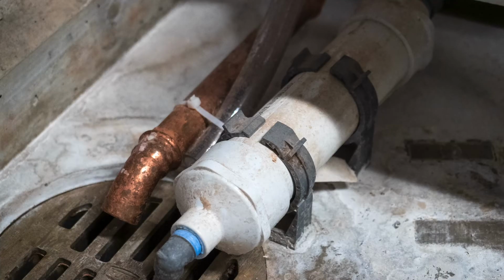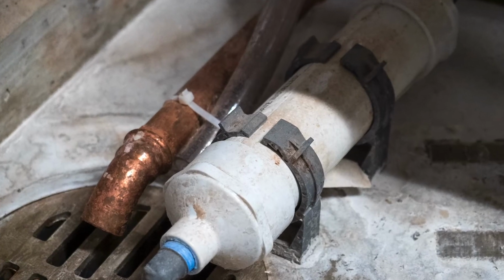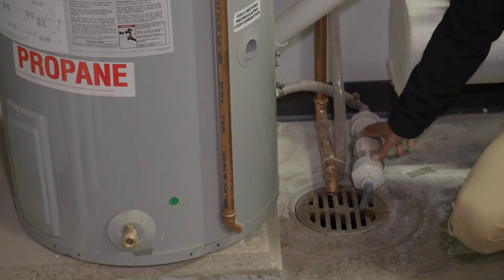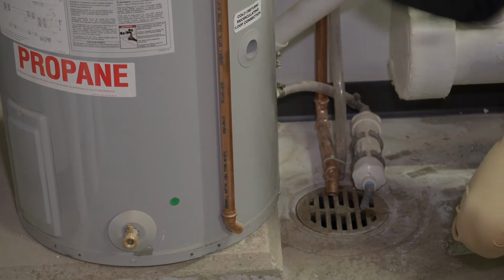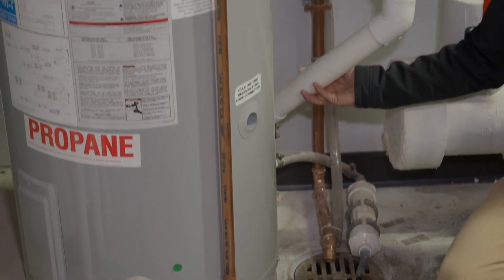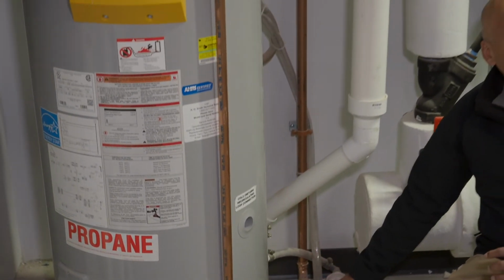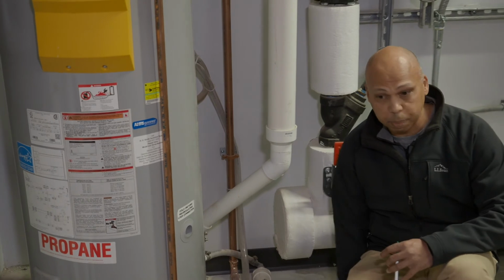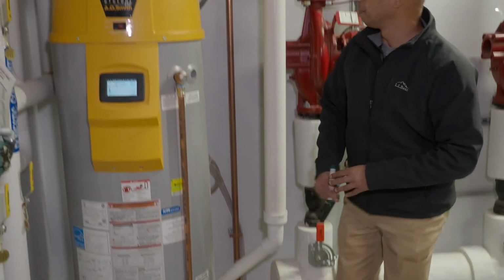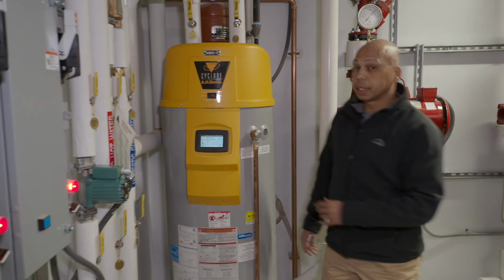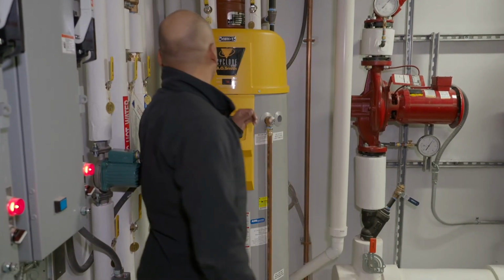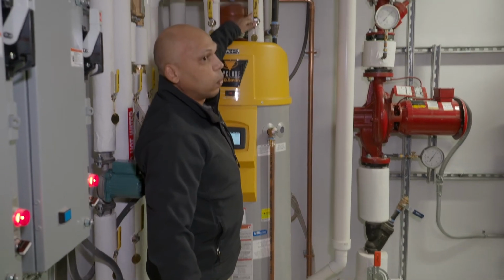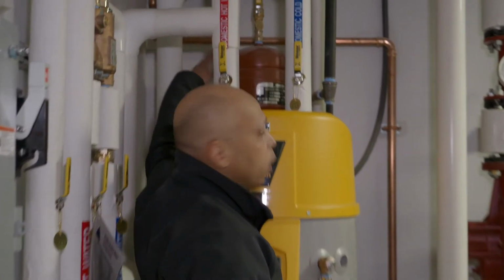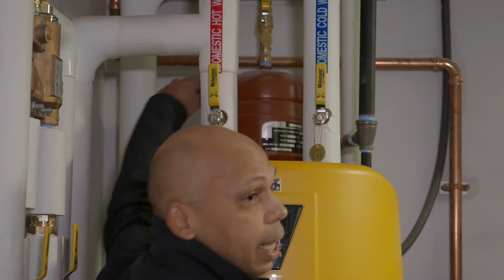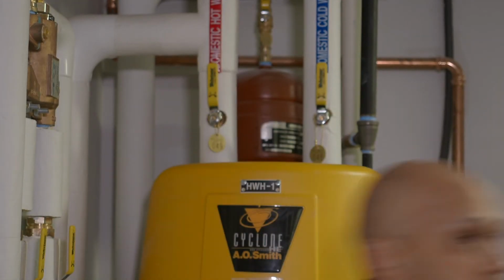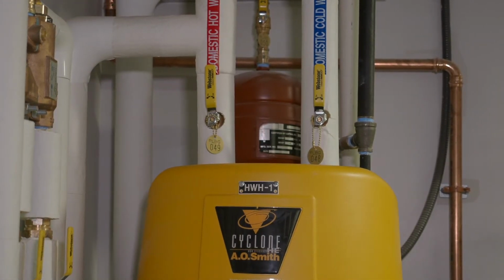You have a condensate neutralizer. You're going to have to replace that every year at least, because the condensate that comes out of the exhaust here is pretty acidic. So you want to have a neutral pH going into the plumbing system. Over here, you have your cold water shut off, your hot water shut off, your thermal expansion tank in the back here, which also is isolated. So those are the main components of this water heater.